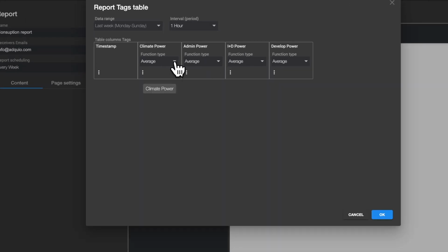Since this column with hourly grouping aggregates several variables that may be collected every 30 seconds, we can decide whether we want this column to show the maximum value, minimum value, an average, or the sum of all values. The most common choice, for example, when reviewing consumption, is to select Average. For the other options, we follow the same steps.